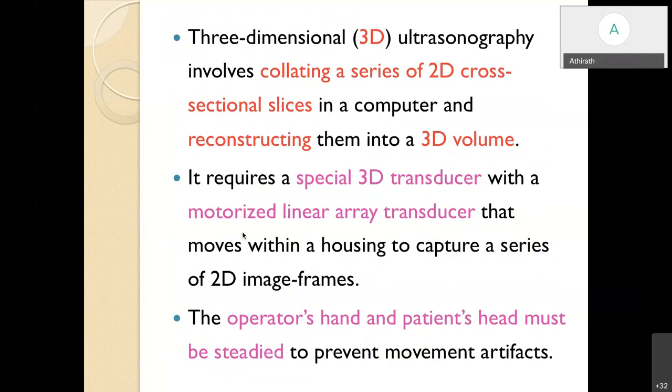What we actually do in this three-dimensional ultrasonography is that we take a series of 2D cross-sectional slices and we collate them and reconstruct them into a 3D volume. But for performing this three-dimensional ultrasonography, we require a special 3D transducer with a motorized linear array transducer that moves within a housing to capture a series of 2D image frames.